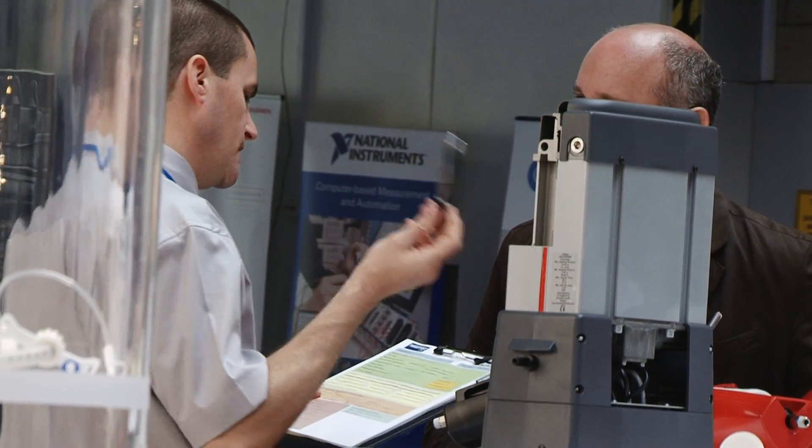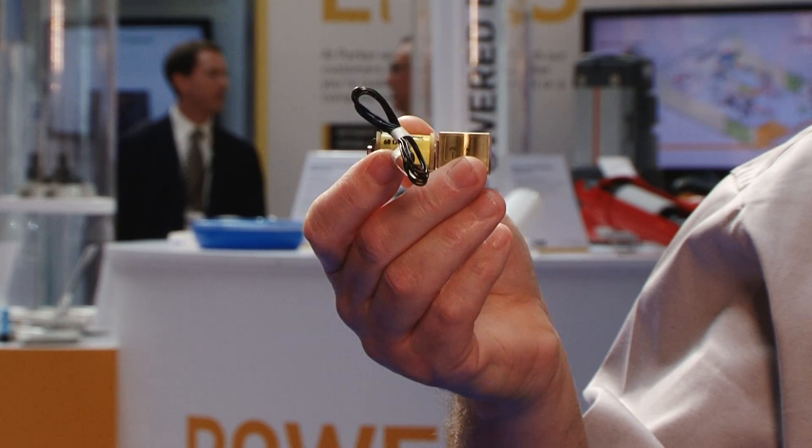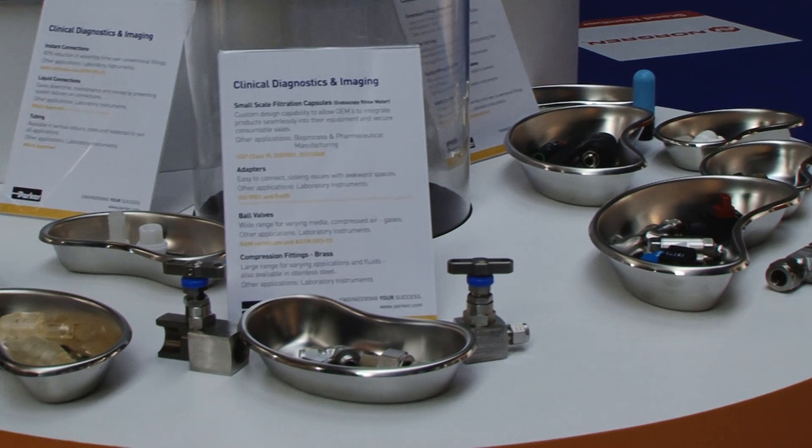Our focus at Parker Hannifin is to ensure that we are engineering solutions that address today's issues in the medical device market. With this in mind, we design cutting-edge valve solutions which offer discernible benefits such as improvement in performance and a cost saving in installation. One example of this is the new VSO proportional valve, which directly addresses the need to reduce power consumption. It consumes 75% less power than competitive valves, thus saving vital battery life.